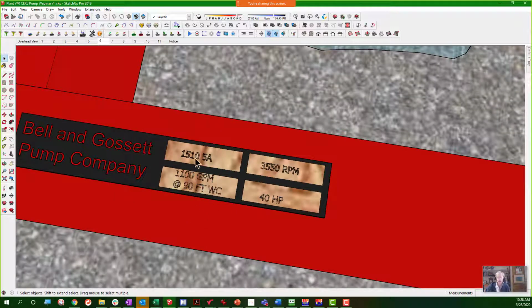Yeah, the reason I went to that was because I know that's a setup in the model. It's a best first cost pump, and so at some point when we get to optimizing the distribution pumps, one of the owners I give them is an owner who, like, I have them do the math and I give them a bunch of different owner types, like an owner that's a 2-year real estate trust, and so they don't really care, like they want 2 years or less. But one of the owners is a long-term owner. They have a 10-year perspective on energy projects, and they just got burned.